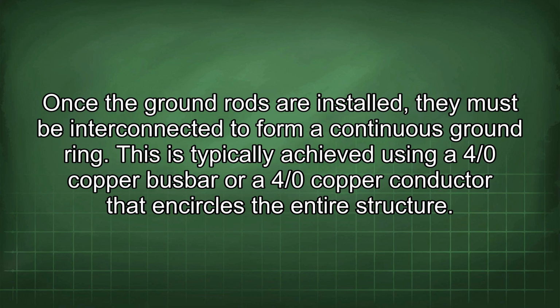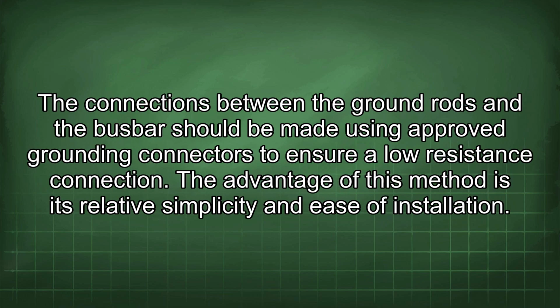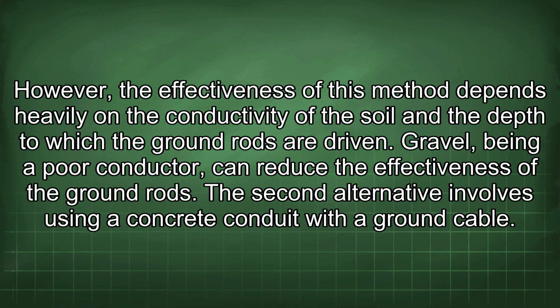This is typically achieved using a 4/0 copper busbar or a 4/0 copper conductor that encircles the entire structure. The connections between the ground rods and the busbar should be made using approved grounding connectors to ensure a low resistance connection. The advantage of this method is its relative simplicity and ease of installation. However, the effectiveness of this method depends heavily on the conductivity of the soil and the depth to which the ground rods are driven. Gravel, being a poor conductor, can reduce the effectiveness of the ground rods.